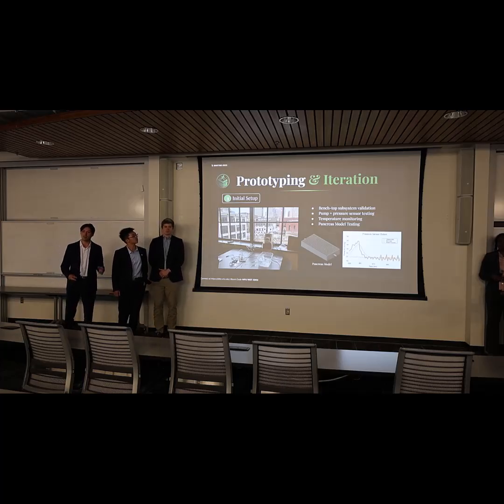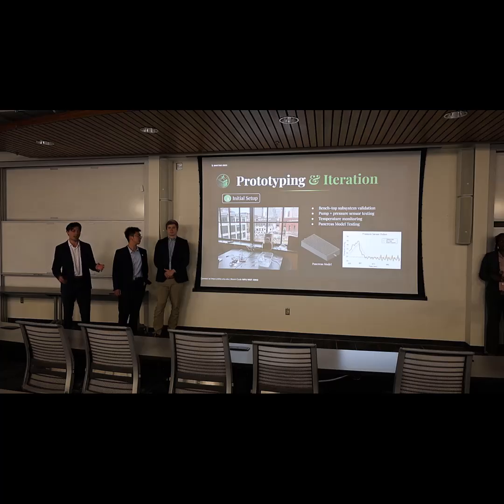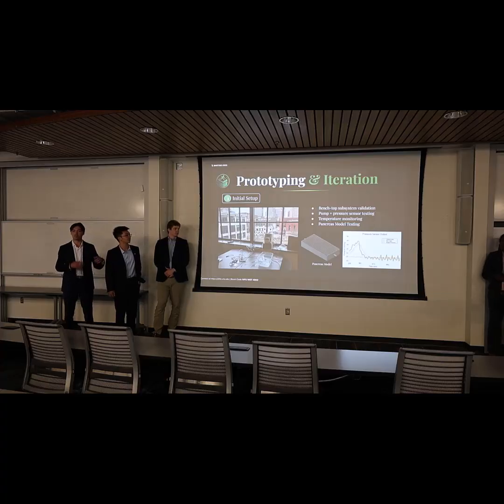And peristaltic pumps are naturally pulsatile, which is good in mimicking the body's heart rate, but bad when you're trying to get accurate readings. So we used a mathematical filter to get a linear line, which you can see more so in the gray. That helps us get good data and actually control the speed of the pump, which in turn helps us control the pressure in the system as a whole.